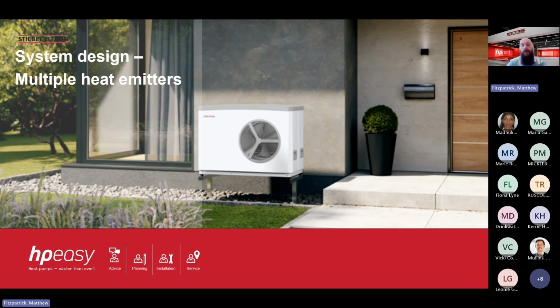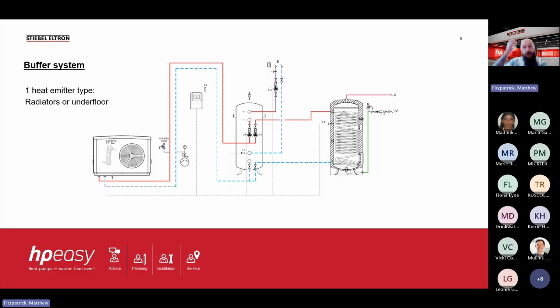So system design and multiple heat emitters. In this example, we just have a hydraulic diagram. We have our air source heat pump on the left with the flow and returns going to a buffer cylinder and also flow and returns going to the hot water cylinder. In this example, there's only one heating circuit. So this could be underfloor or radiators. We're going to target one temperature in the buffer cylinder. It depends on the heat curve and weather compensation, but we'll say the maximum temperature is 38 degrees. So there's only one temperature to be delivered to our heat emitters, and this could be underfloor or radiators.